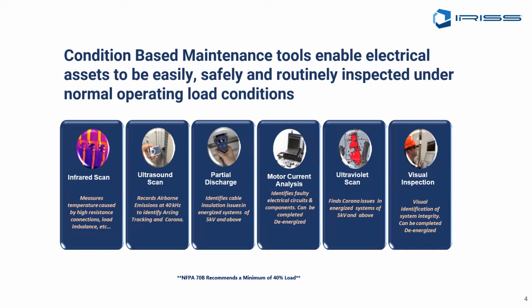So we can do infrared. We're going to find high temperature, high resistance connections. Again, ultrasound. We're going to record electrically arcing, tracking, and corona. All three of those give off an ultrasound noise above the 20 kilohertz range, above the range of human hearing, but that we can detect using handheld ultrasound equipment.